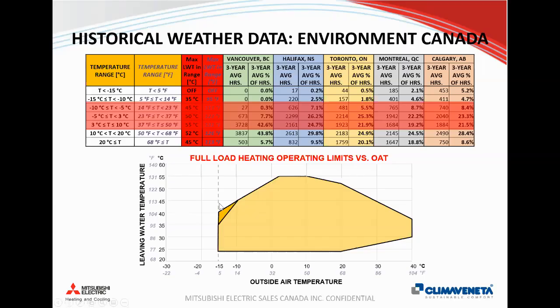So the question and rebuttal I usually get from engineers is, well, we can't really use 35 degrees Celsius as a design temperature in our system to actually meet the heat loads in the building at -15. And while that might be true, there are different systems that you can look at using lower water temperatures, because in the low carbon economy, there's more and more talk about condensing gas boilers becoming the standard in Canada post 2025. And still with air-to-water heat pumps, for in-floor radiant systems, you can still use a lower supply temperature of 35 or 40 degrees.